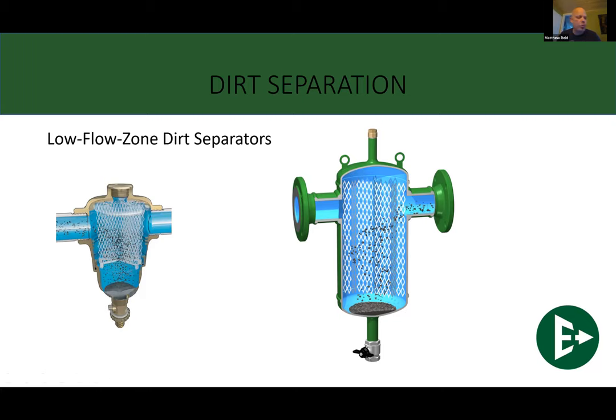Now, before I go any further on this one here, air separators have become standard in the code, while dirt separators are not. To that, I would only say this. The idea of not putting a dirt separator in a hydronic system, I would give you that exact same rebuttal. Would you ever install a furnace without putting a furnace filter in? Because it does the exact same job, protecting the heat exchanger, the big part of the system, from getting all clogged up with garbage. So if you use one system or another, I do care. I like these things better than the others, but you've got to use something to get the dirt out of a system, and dirt's always going to form.